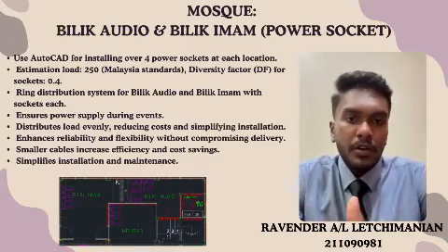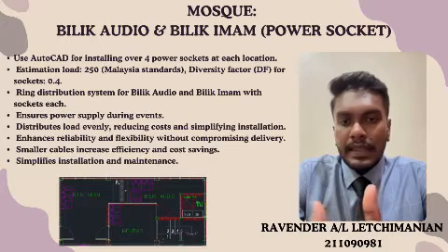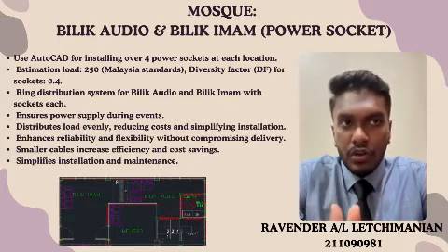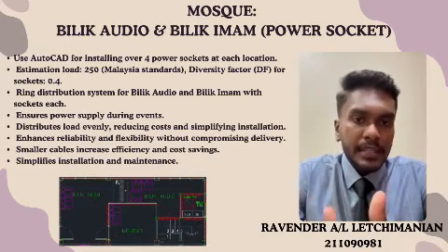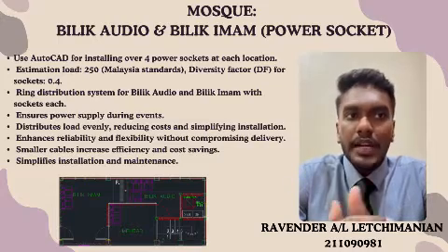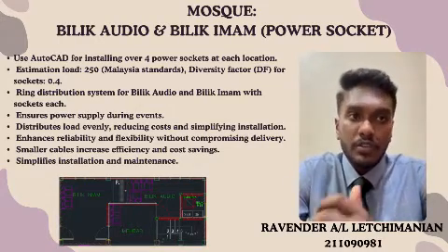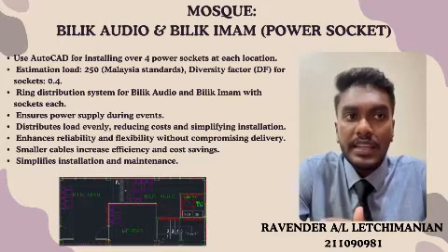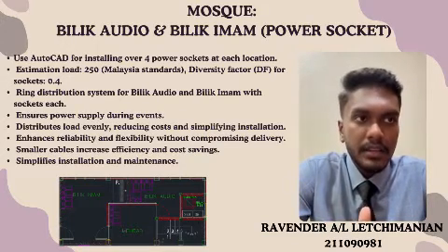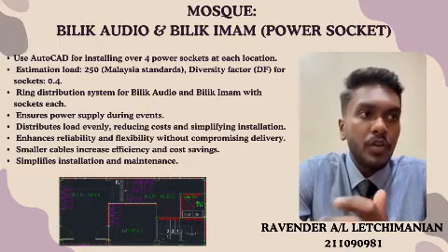Furthermore, let's talk about the power sockets that have been used at the Bilik Audio and Bilik Imam for assignment 2 at the mosque. Throughout the AutoCAD software, we need to install more than 4 power sockets for each location. The estimation load is 250 as national standard. The diversity factor is 0.4 for the socket.